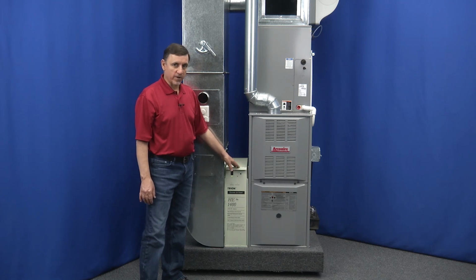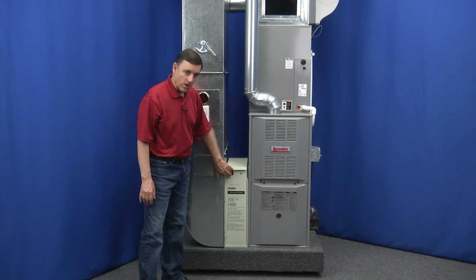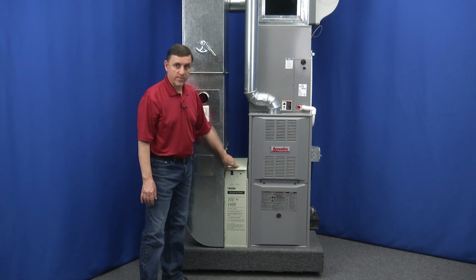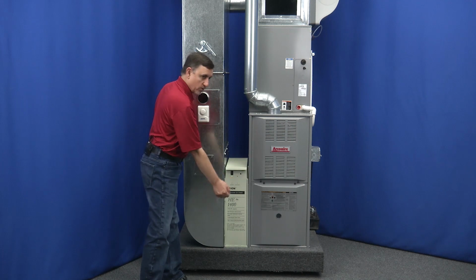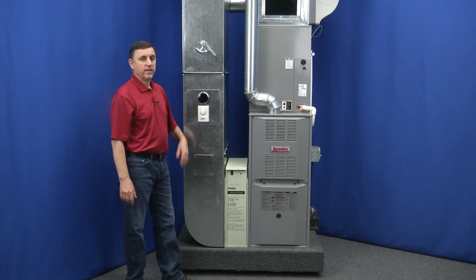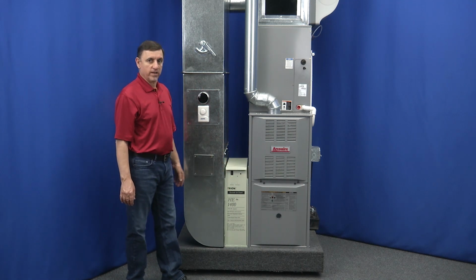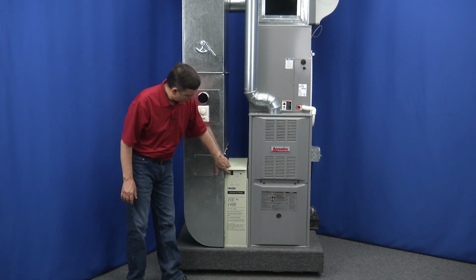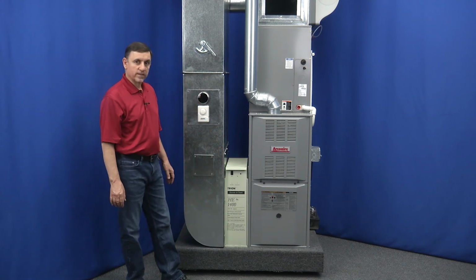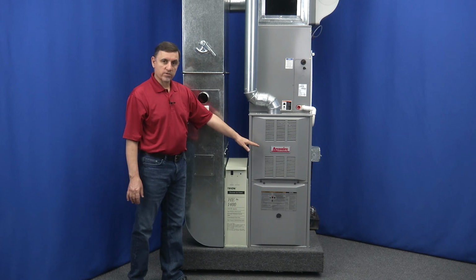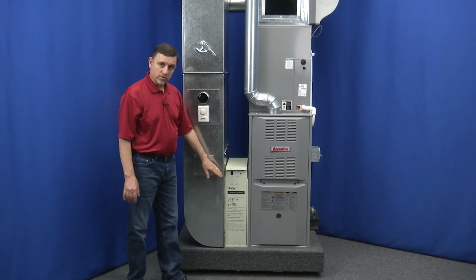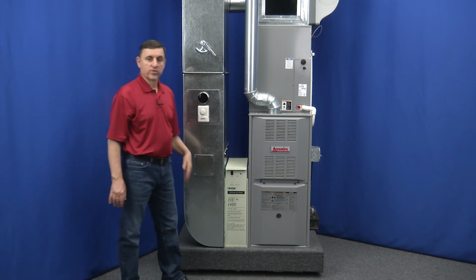And it needs to be calibrated, and it's calibrated every time the power is turned on or off to this thing, every time there's a power outage, every time you remove the door, put the door back on, it goes into a recalibration mode. So here's how that works. So I'm going to turn this thing off. Right now the blower is turned off, the air cleaner is turned off. I'm going to leave it off for a minute here, and then we're going to turn it back on and let it calibrate.